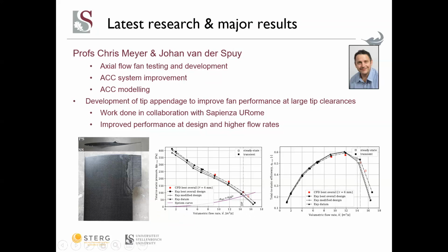And on the right-hand side, we can see that the efficiency is increased at the design flow rate and at higher flow rates, again, for the modified fan versus the standard fan.